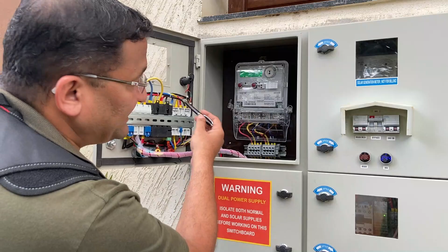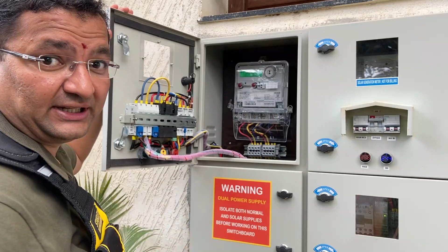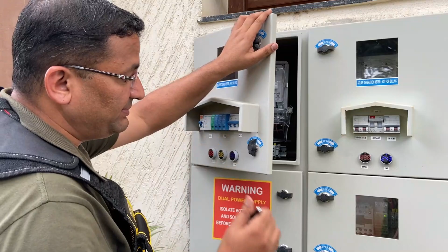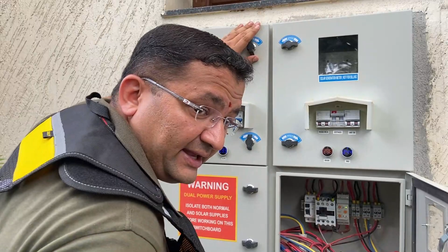One phase, that is the lighting phase, is taken into the inverter. So one phase is tapped from here and this goes into the inverter. Before it goes into the inverter, this one phase, from this MCB, is taken into our first level of protection. Here we have an ELCB.